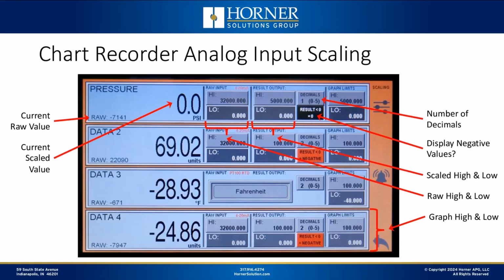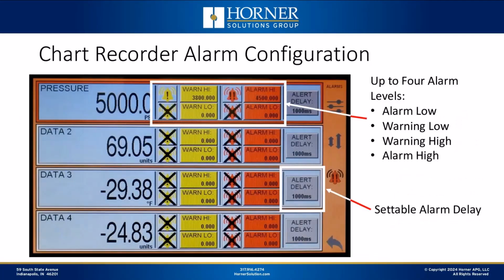And then independently of how you scale the input side to engineering units, you can decide the low and the high limit for how you want to graph the data. So maybe in our example where it's 10 to 100 pounds per square inch, maybe we're really only interested in graphing between 10 and 30 PSI. So we can decide, okay, we're just going to graph between 10 and 30 because we know in our particular application that sensor is never going to get above 30, for instance. So these are some of the scaling parameters that you can access here from the touchscreen.